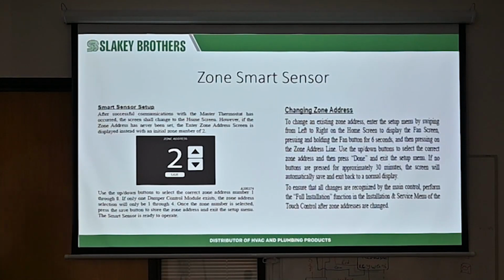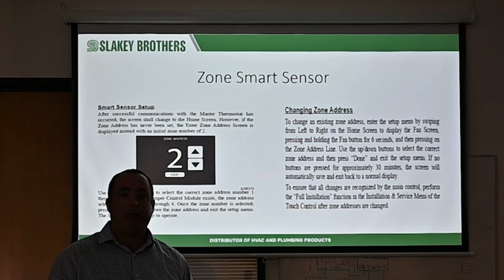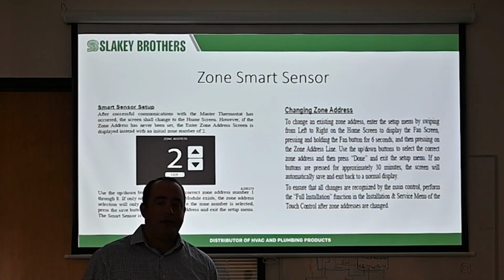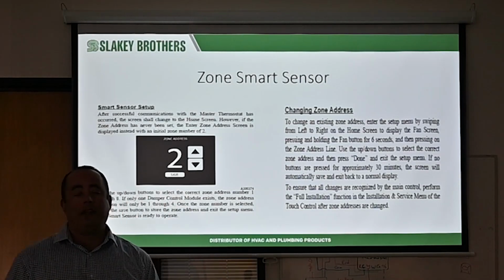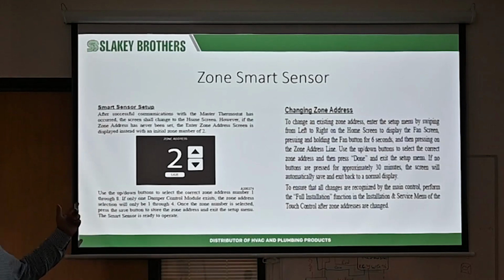If you have a zone system, power up everything so that nothing gets confused later on. This is on the smart sensors. Every smart sensor won't self-configure what zone it is. It will immediately just say I'm zone 2. So one problem that happened is people forget to go in there and change the smart sensor zoning.